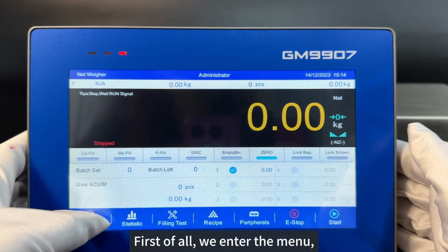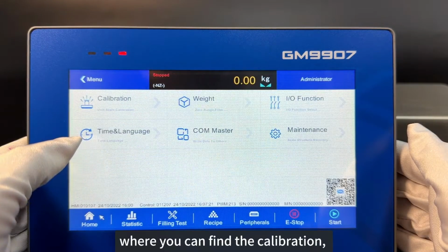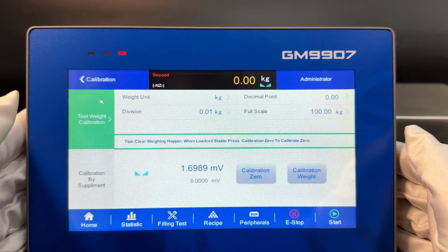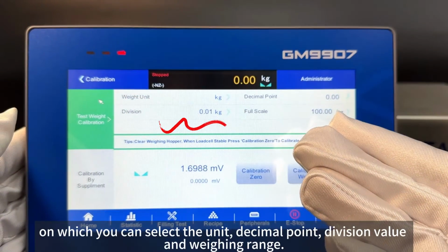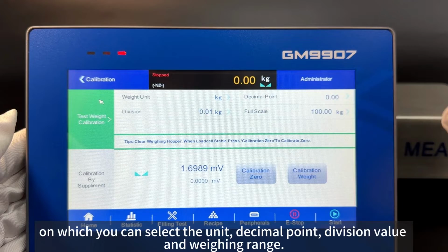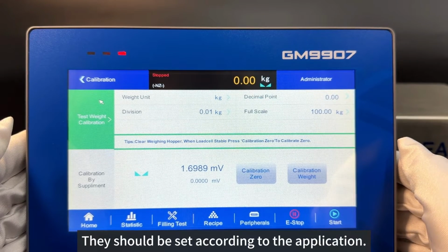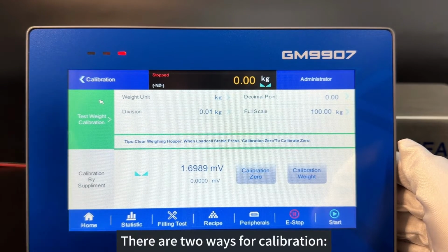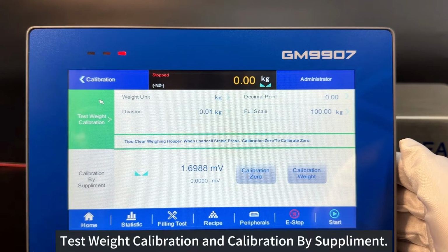First of all, we enter the menu, where you can find the calibration, on which you can select the unit, decimal point, division value, and weighing range. They should be set according to the application. There are two ways for calibration: test weight calibration and calibration by supplement.